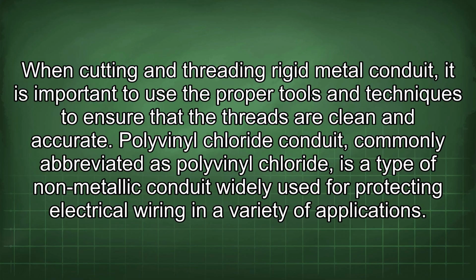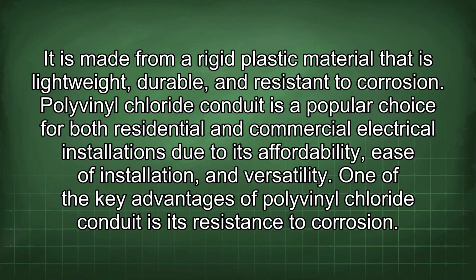Polyvinyl chloride conduit, commonly abbreviated as PVC, is a type of non-metallic conduit widely used for protecting electrical wiring in a variety of applications. It is made from a rigid plastic material that is lightweight, durable, and resistant to corrosion. Polyvinyl chloride conduit is a popular choice for both residential and commercial electrical installations due to its affordability, ease of installation, and versatility. One of the key advantages of polyvinyl chloride conduit is its resistance to corrosion.